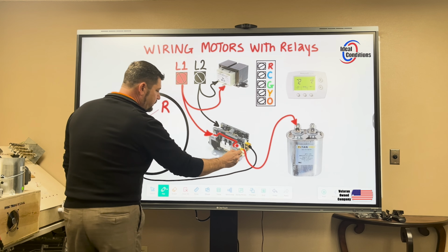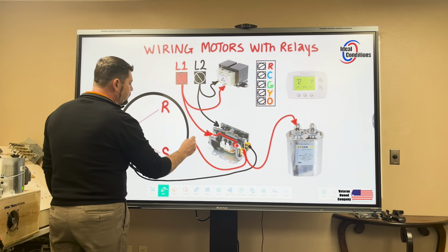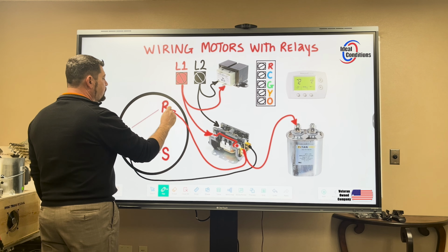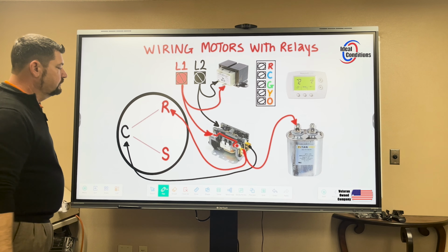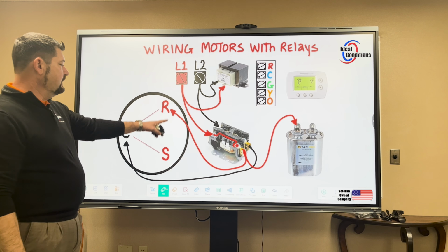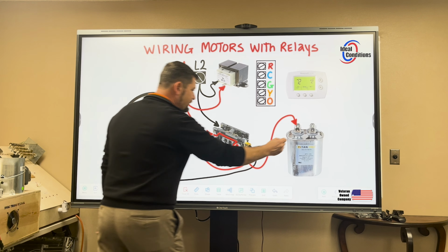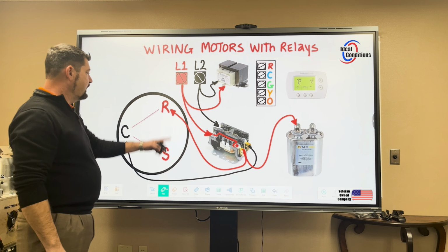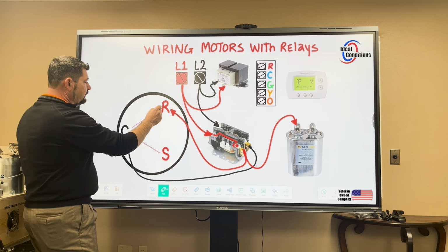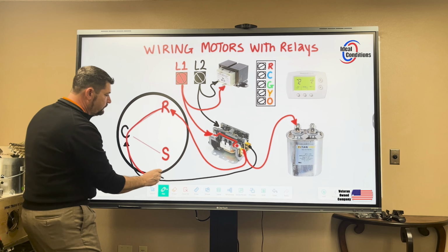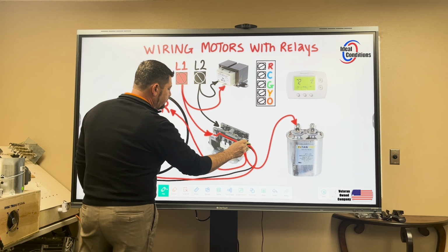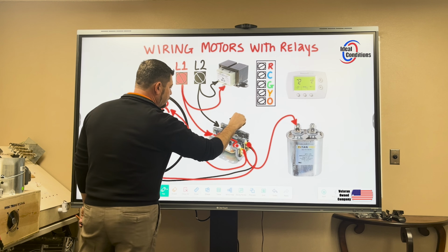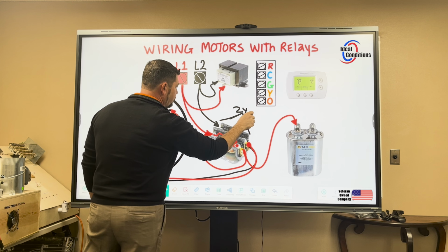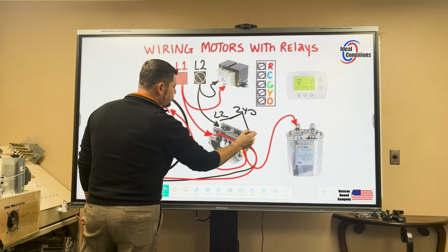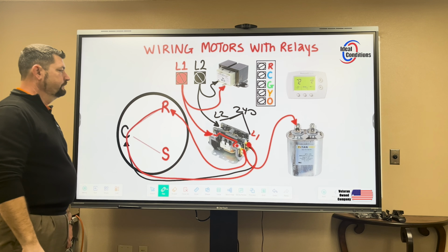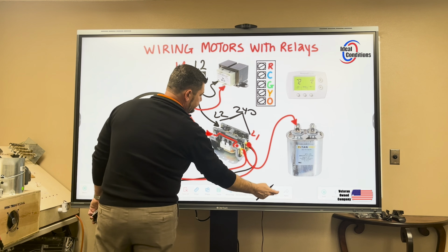And also I'm going to come out of this and run up to my run winding on my fan motor. The moment I did this, I didn't even complete my start winding circuit, but I actually had electricity come back through here and all the way over to here. So now I have 240 volts because I have L2 and L1 present. See how that works? Let me clean that up.